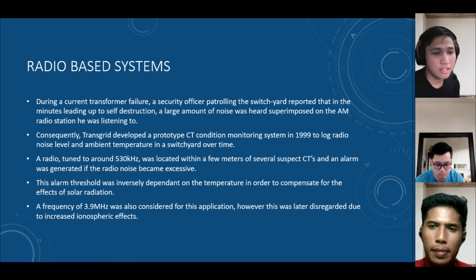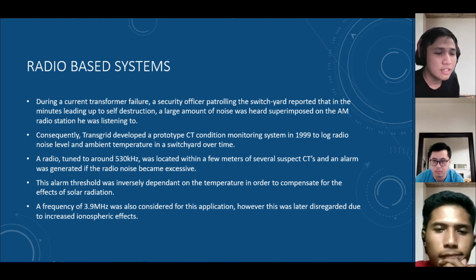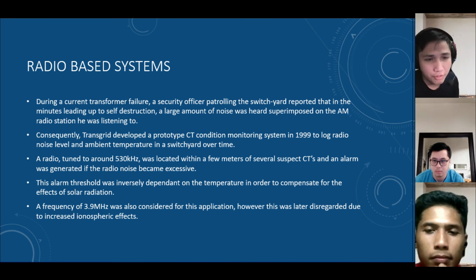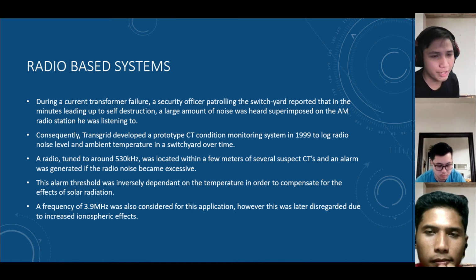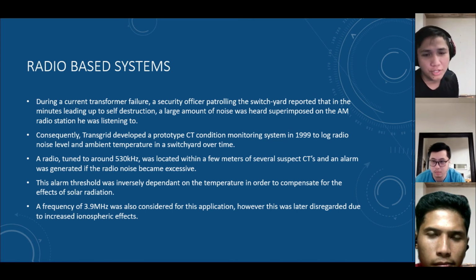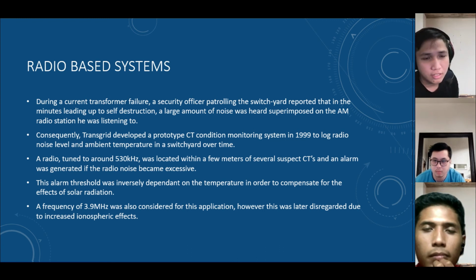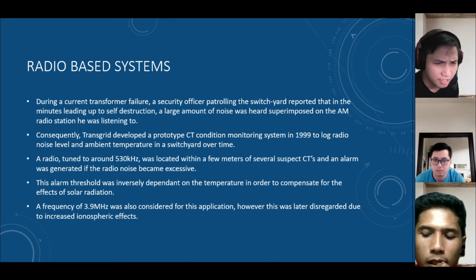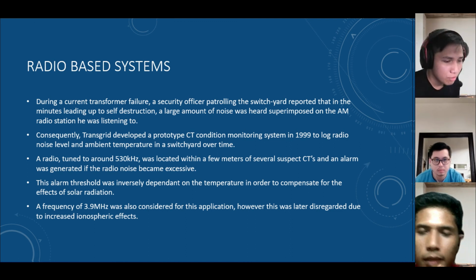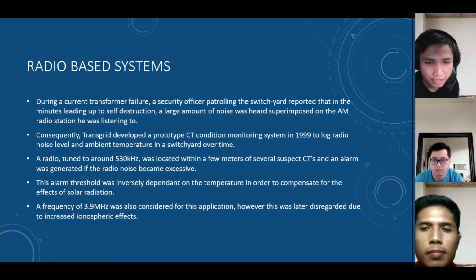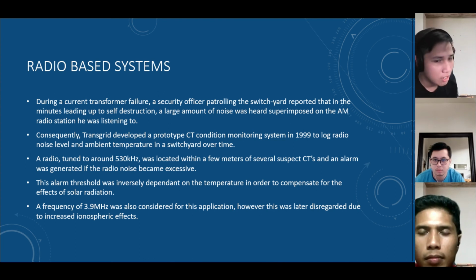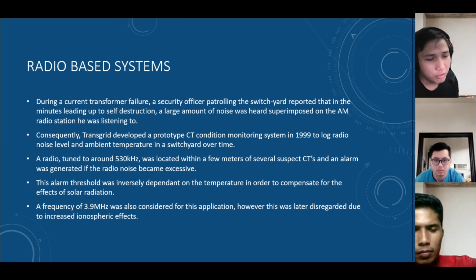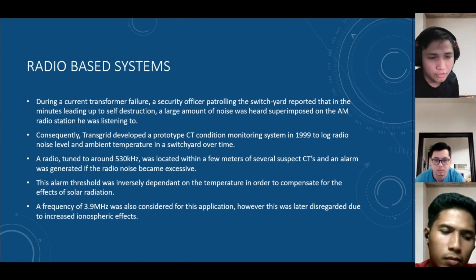So let's move to the next method, which is the online techniques at Basewater. The first online technique is the radio-based system, which is based on radio frequency. During the transformer current failure, a security officer patrolling the switch yard reported that in the minutes leading to the failure, a large amount of noise was heard superimposed on the AM radio station he was listening to. Consequently, Transgrid, the network provider, developed a prototype current transformer condition monitoring system to log radio noise level and ambient temperature in the switch yard over time. If anything happens to the system, this will provide an initial warning of any changes to the frequency of the system.